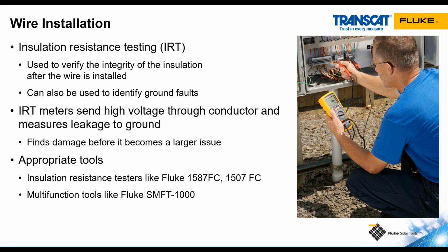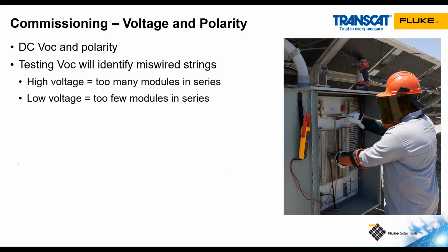The 1587, 1507, and the SMFT 1000 are not capable of testing above 1000 volts, so they're good for the lower voltage systems, but you really should be using something a little higher voltage with the utility scale projects. The SMFT 1000 is a solar multifunction tool. It can do insulation resistance testing up to 1000 volts. It performs essentially every test that the IEC standard recommends, and we'll see that as we go along through this presentation.